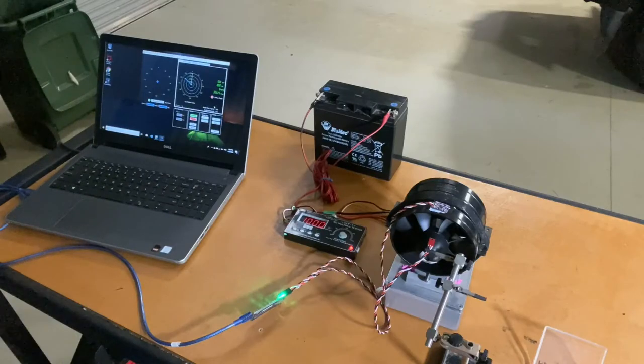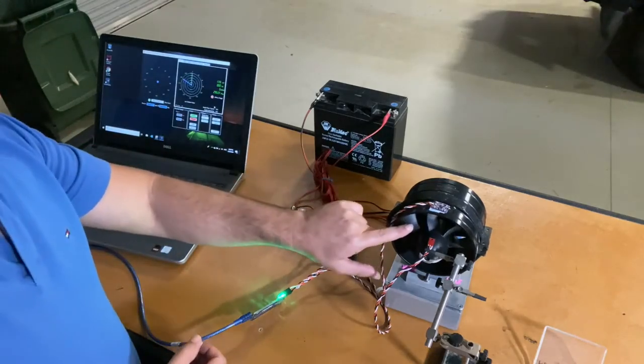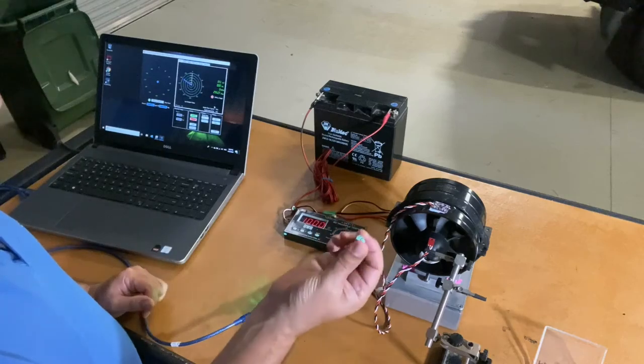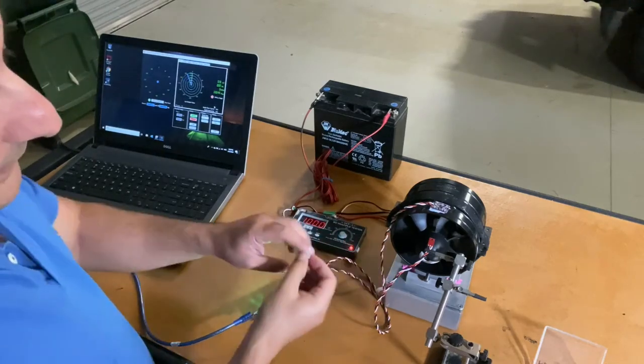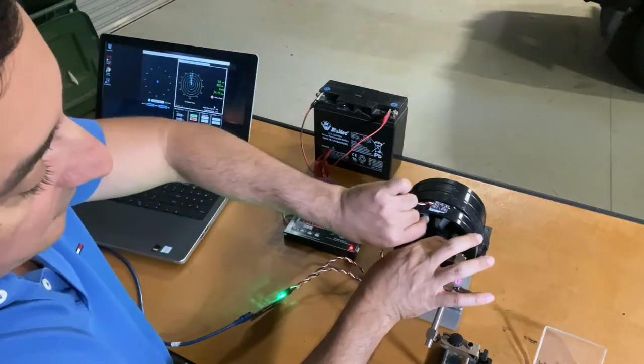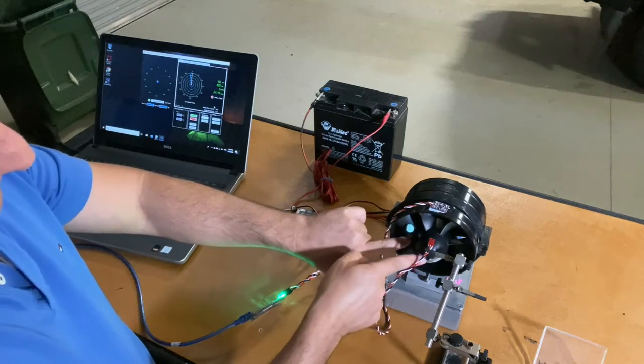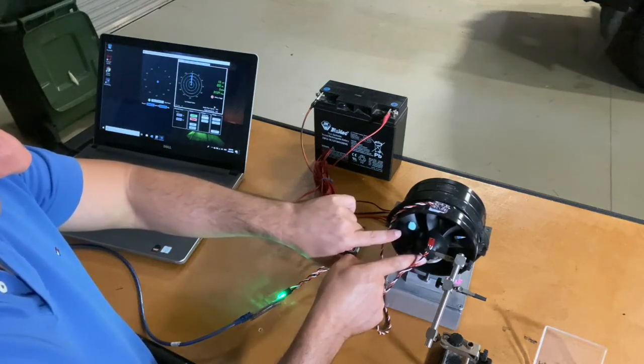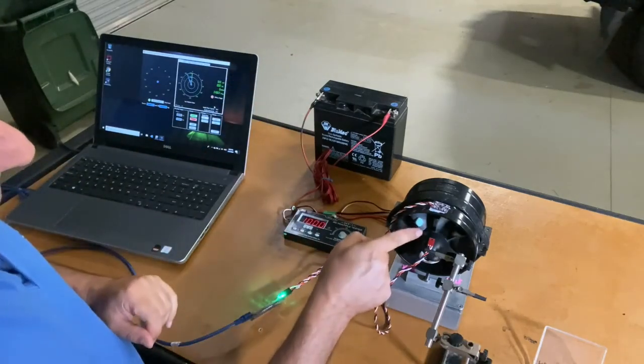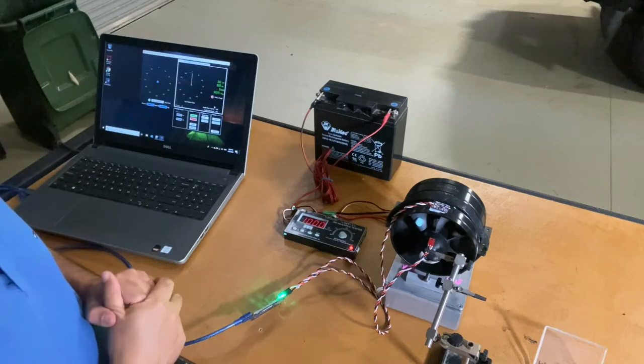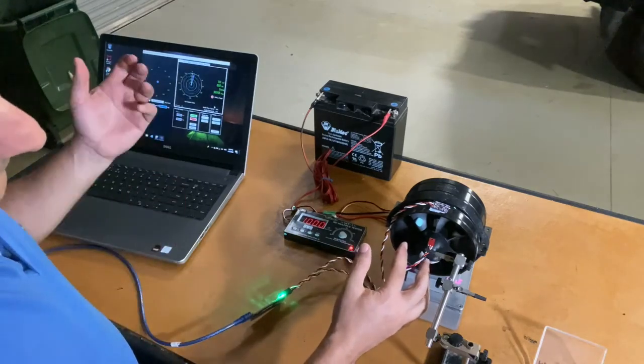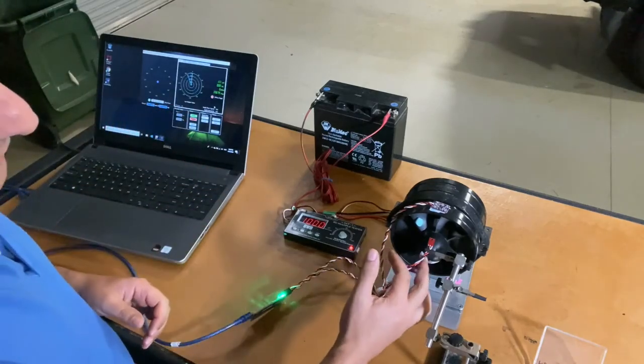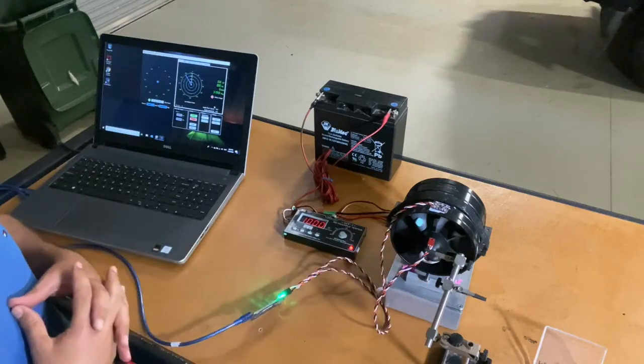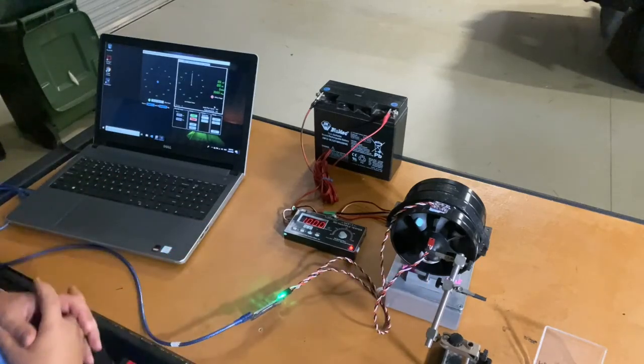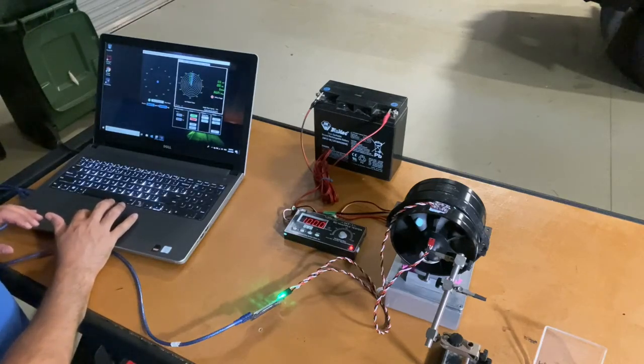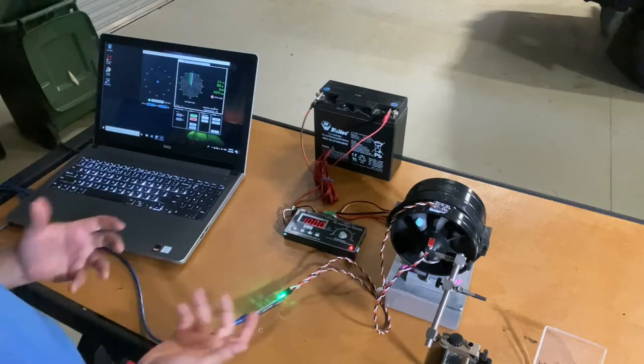So if I was to demonstrate that, the residual imbalance on the EDF would be, for example, this piece of blue tack. In theory, if there was still residual imbalance, it would be this piece of blue tack located at a certain radius from the center of the axis of the EDF. So for example, if I had a 5 gram residual imbalance of the EDF located, say, 10 millimeters away from the center of rotation or the axis, then my residual imbalance would be 50 gram millimeters. And so the quality limit actually evaluates what that residual imbalance does after you do your balance process.